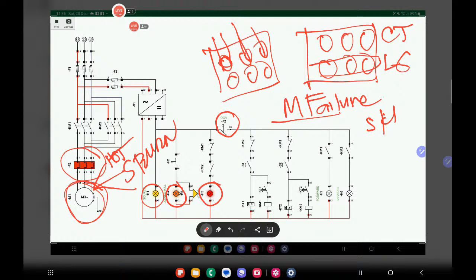So if you check all these conditions and the motor is not hot, it means it didn't run in a much effort way. No? So there would be a prolonged running just before it overloads, because sometimes if you have faulty electronic equipment, like your F2 itself has the problem, then this will also activate or trigger the alarm even if you don't have overloading on your system. Don't rule out that possibility, because there are instances where I needed to change the overload relay.